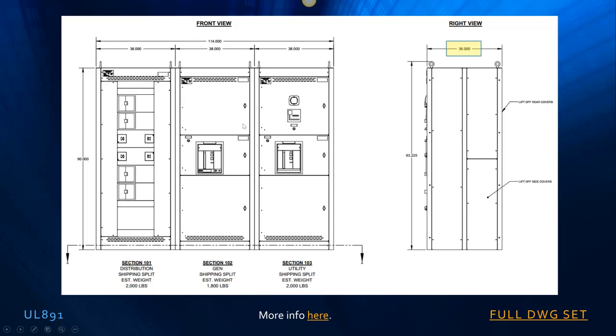In case some of you are wondering how it's connected, for this distribution part of the board, these are wireways. They become unbolted and the contractor will run wires from the bottom or top down this wireway to the breakers. Over here, these cabinets are hinged, and if you were to come up from the bottom, this door would open and the cables would come in the bottom and into the breaker here.